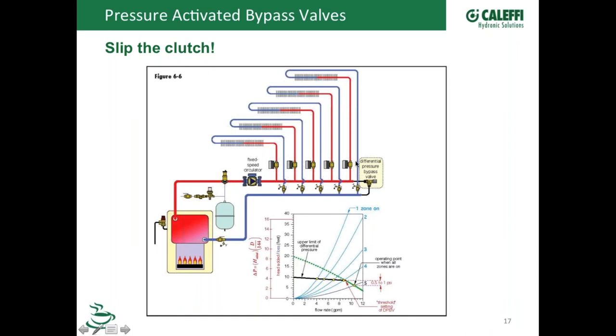You can get into a condition where if this is a very small zone, maybe a half inch baseboard loop here, and you still have a 12 gallon a minute pump that you're trying to shove through that half inch circuit, you're going to have some noise and you might have some complaints from the customer on that. So that valve we still offer in a couple different sizes. Nice about the Caleffi one, it's got very low pressure drop. Some of them out there on the market, as you start looking at the CV spec on it, they've got a lot of pressure drop. You're burning up a lot of your pump head just going through the valve.